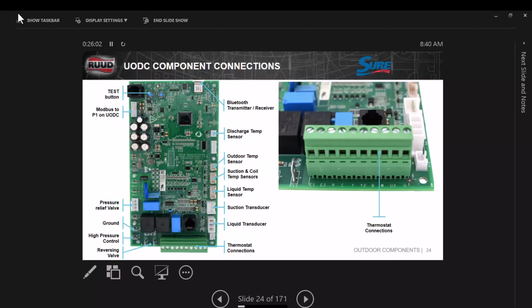Looking at all the connections on the board, if we go up to the top, that Modbus connection there that talks back and forth to the boards, there's the connection for that pressure relief valve. Of course, ground, high pressure control, reversing valve down here. Liquid transducer. So we've got some transducers on here. The transducer is what reads the pressures in the system.